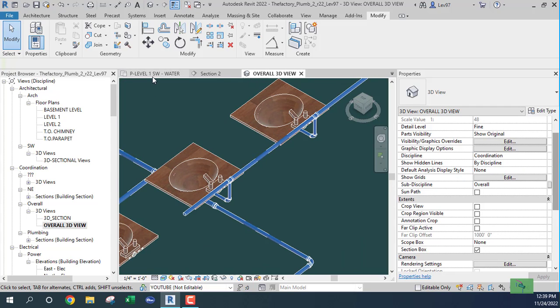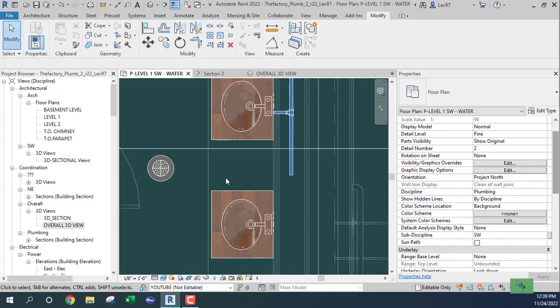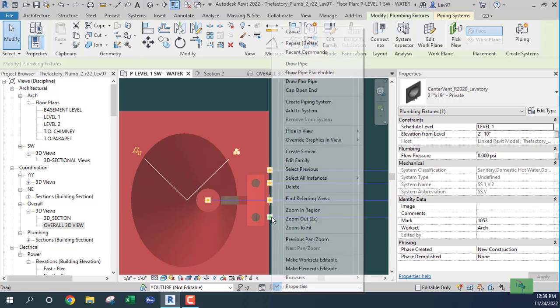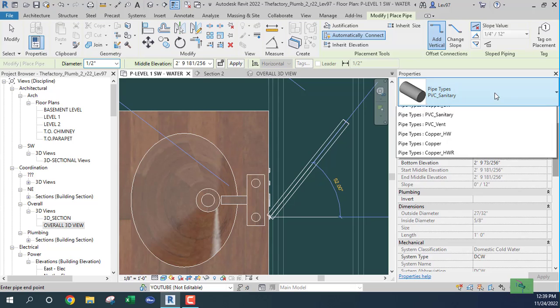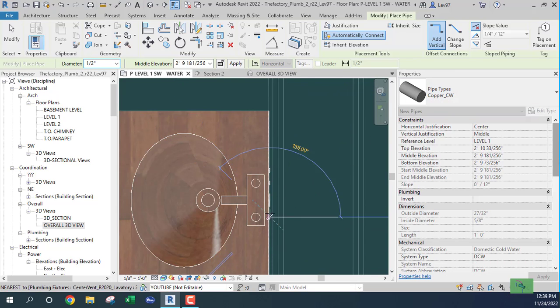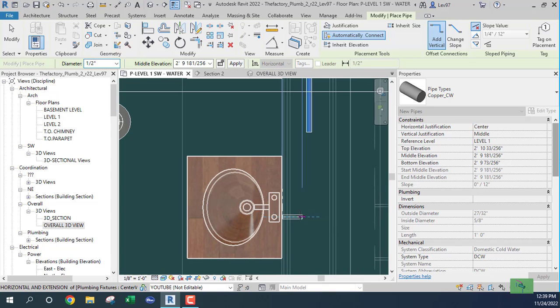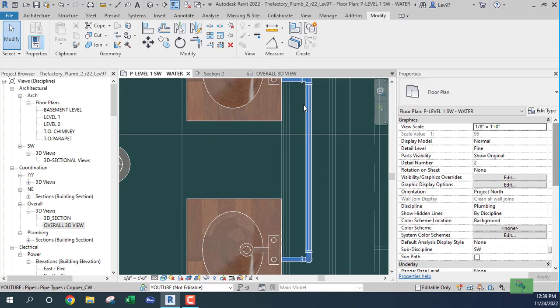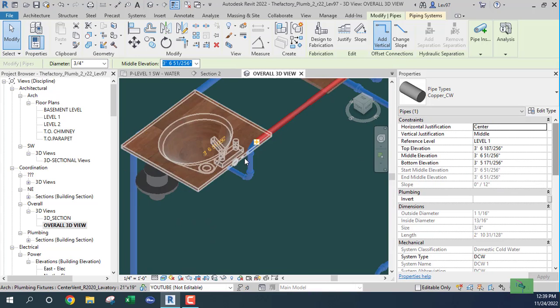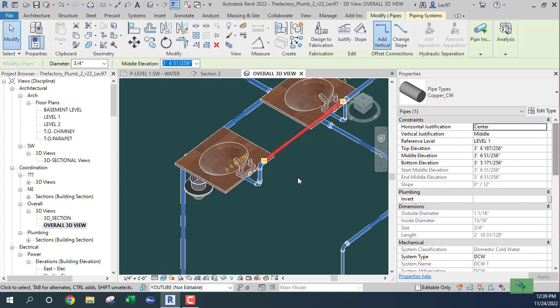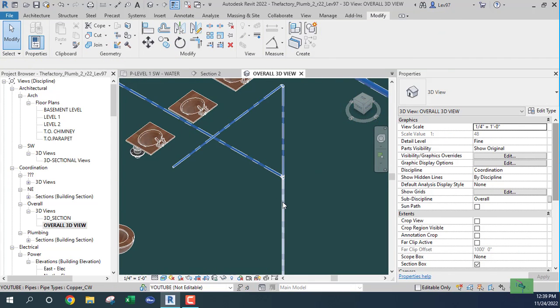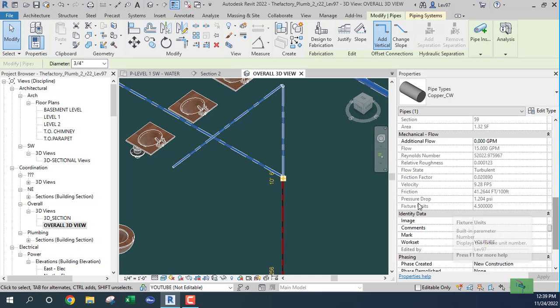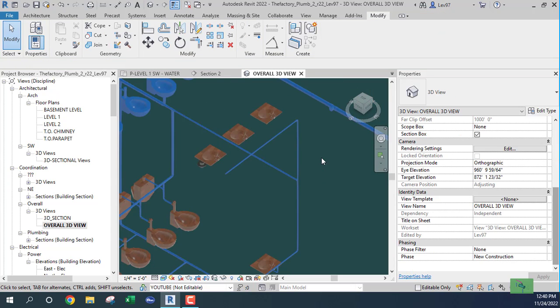Now we can go back to the first level. I need to change that line to a three-quarter — maybe a one-inch, because I'm feeding up to these on the second level. There are three lavatories, so I have nine fixture units. But I'll keep it at one inch. I do need to reduce it. These two segments of pipe and this elbow are going to be three-quarter inch. So I'll change that to three-quarter inch. And then three-quarter inch on the run — okay, that looks good. Fixture units: 4.5, 15 GPM.